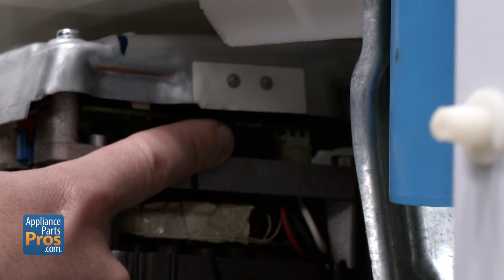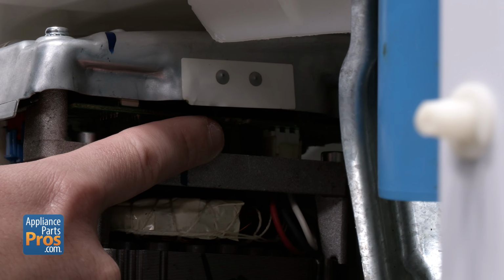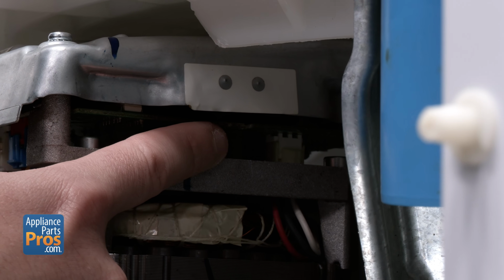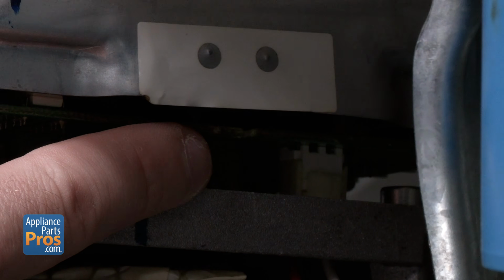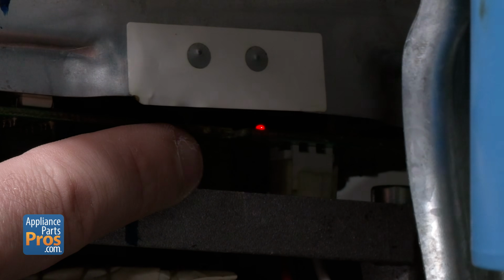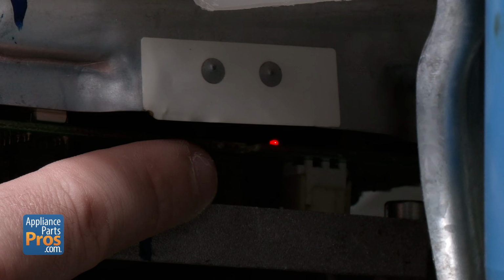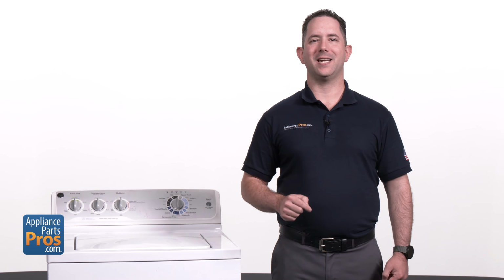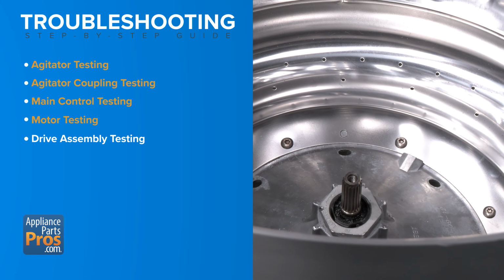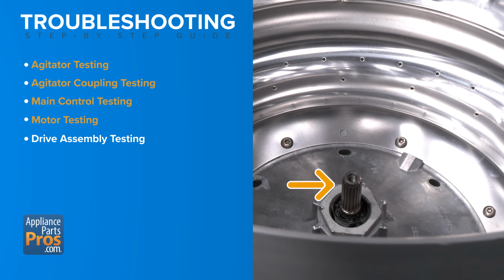Now locate the LED indicator on the top of the motor and observe the flash pattern. If it flashes once, then pauses for a long time, or flashes 3, 5, or 9 times, the motor has failed. If it flashes 1 second on, 1 second off, continue troubleshooting. Any other flash pattern indicates a specific fault, which should be cross-referenced with the model's technical sheet. If everything else has passed testing, the drive assembly is likely at fault. To confirm, we'll inspect the shifter and test the actuator coil for resistance.